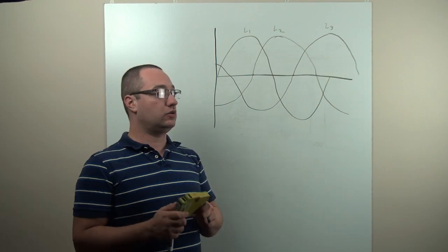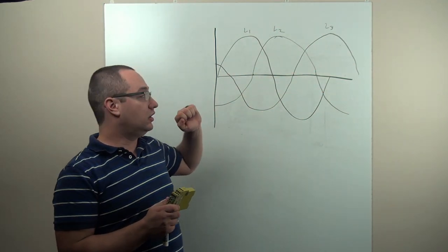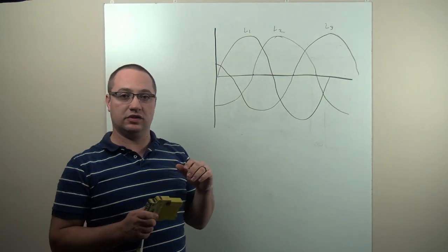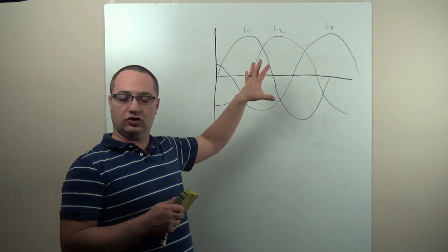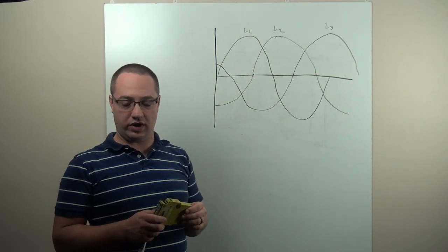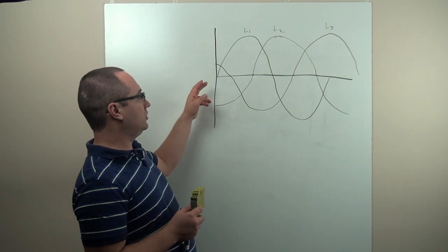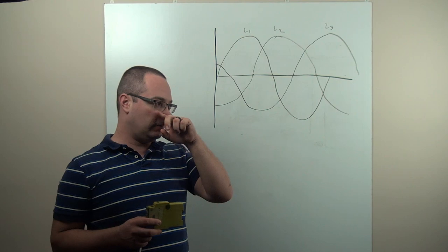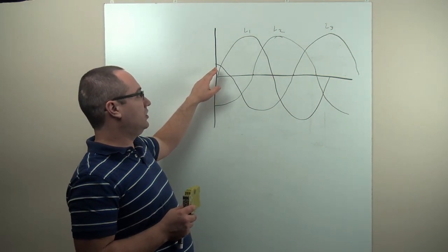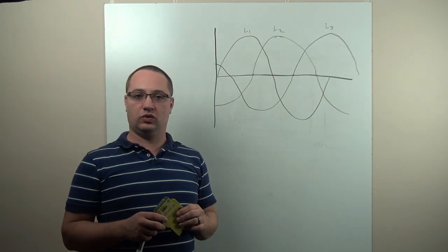What does it mean if the power is good? It means that all three phases are present. The voltage of all three phases is neither too high nor too low, both in reference to each other and to ground. The symmetry of the phases is correct, meaning the shape of the sine wave isn't all contorted.